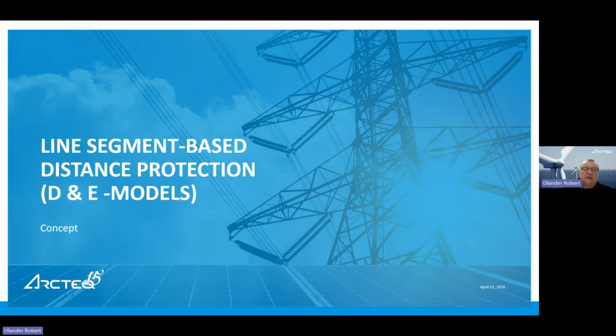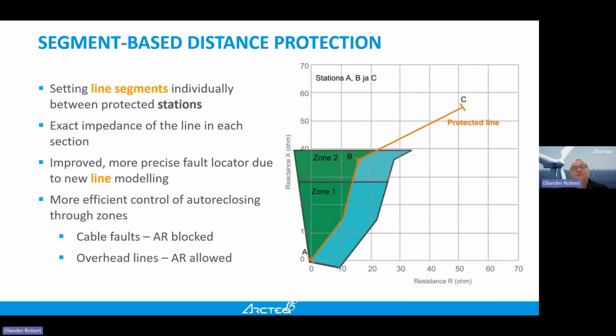And then if we go to distance protection, here we have a little bit more news than in the line differential. So we call our distance protection segment-based distance protection. And this is based on the idea that typically in a distance protection, you can have up to 5 zones. I think in this case we are representing two zones, but still within a zone you will have several line segments. You can have an underground cable, you can have an overhead line, you can have a different overhead line, and they all have different parameters.